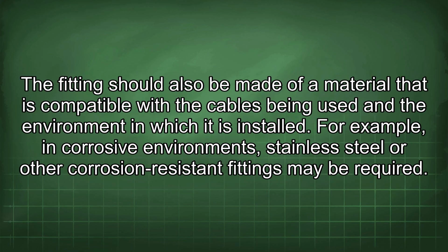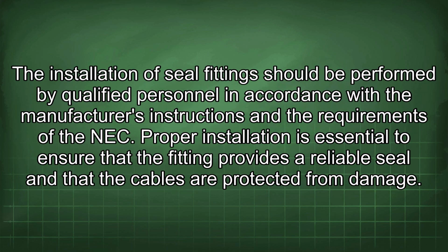The fitting should also be made of a material that is compatible with the cables being used and the environment in which it is installed. For example, in corrosive environments, stainless steel or other corrosion-resistant fittings may be required. The installation of seal fittings should be performed by qualified personnel in accordance with the manufacturer's instructions and the requirements of the NEC. Proper installation is essential to ensure that the fitting provides a reliable seal and that the cables are protected from damage.